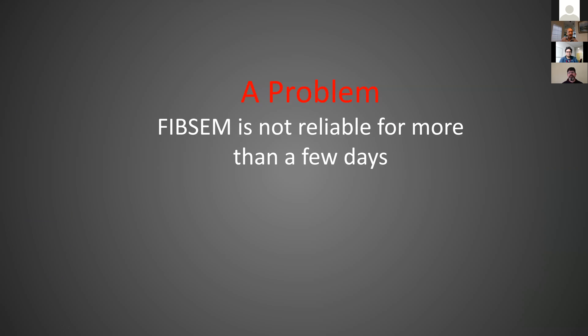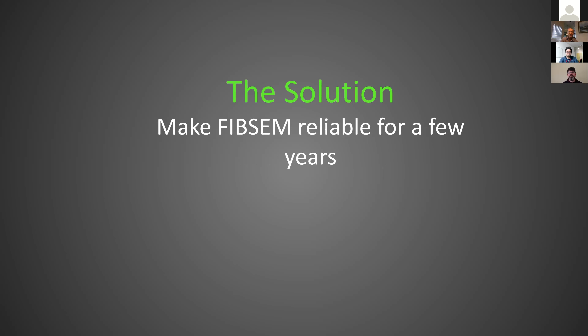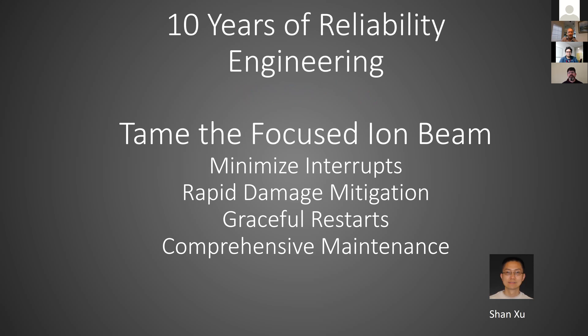FIB-SEM was not reliable for more than a few days, so we had to think deeply and apply all our physics knowledge. The solution: make it reliable for a few years. Shan Xu is the hero here — he optimized these machines to achieve a very high degree of reliability, which is no small task. Countless frustrating and sometimes amusing things interrupted operation. He minimized interrupts; even if something happens we can restart the machine gracefully without losing data, for example if a pump blows up.